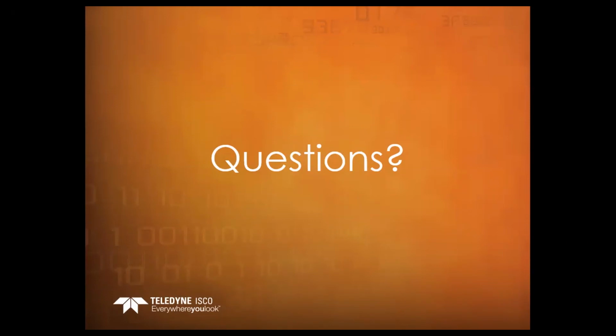Okay. Here's another question. Previously, we've used the 100 HLF dual pump system for work with methane. We're looking forward to expanding our capability with a second system. Now that the 100 HLF dual pump is no longer available, we considered a 260 HLF dual pump, but found that the available volume was too large and the pressure too low, so it's not suitable for meeting our objectives. We're considering the 100DX dual pump. Is that a safe operation for those pumps with a flammable gas, such as methane?